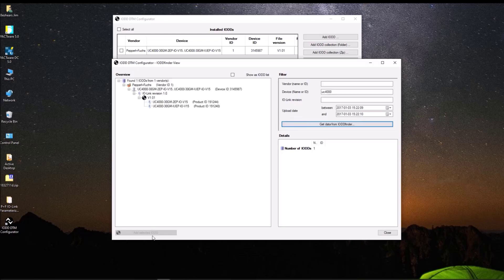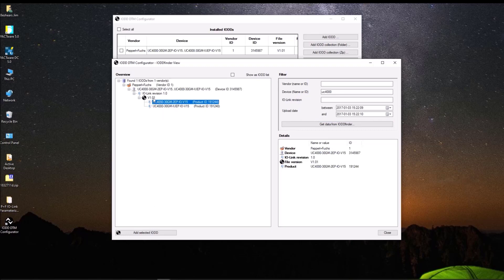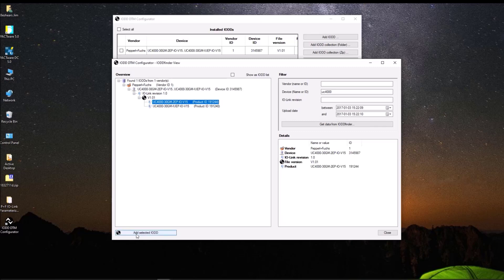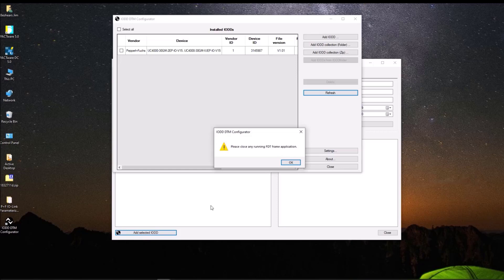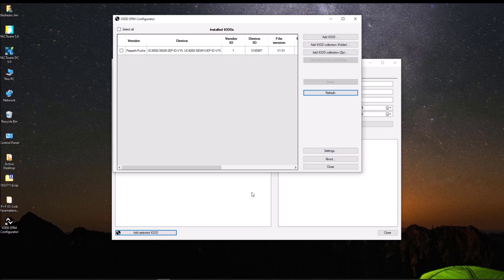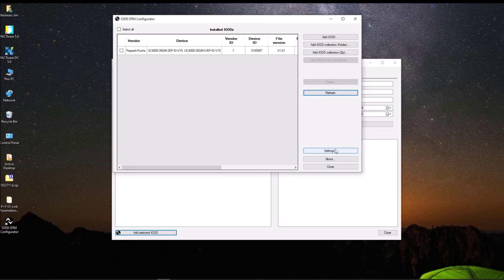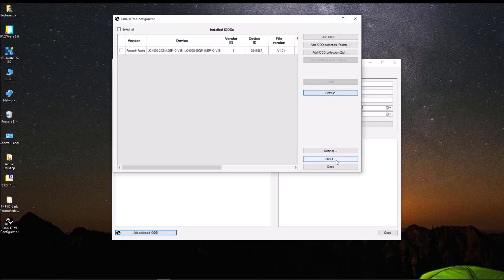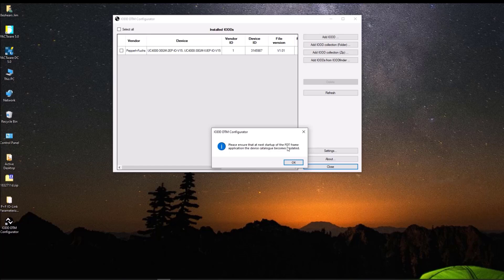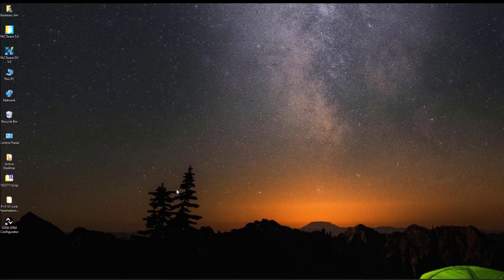Since we have that, we want these two. So that will be included in this file. So we'll click on one of them. Down at the bottom, it says Add Selected IODD. We'll click on that. We don't have any FDT frame applications running. So we'll click on that. And we would in this case want to replace it because I already have it. You won't have that if it's not available. So since we have everything on there, you can see we've got the 2EP and the IUEP version. We are going to let's refresh it just to make sure. Okay, it did keep it. Let's close this. This is very important here. It says please ensure that at the next startup of the FDT frame application, which is PACTware, the device catalog is updated. So we want to make sure we do that.